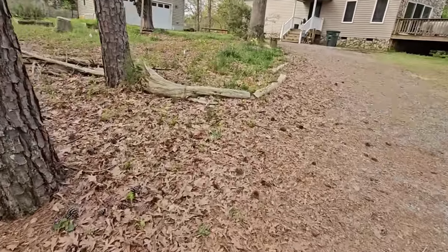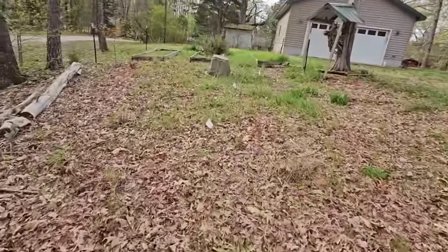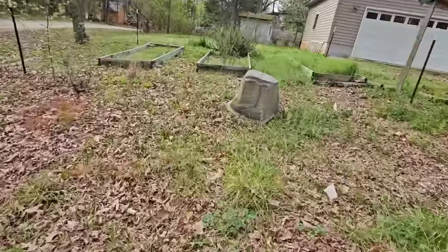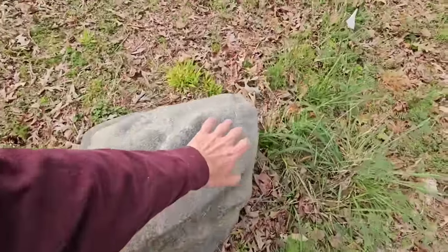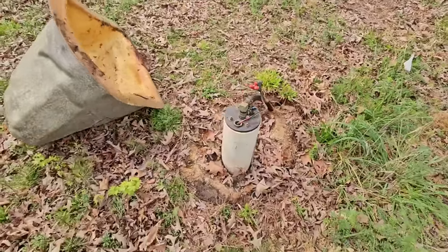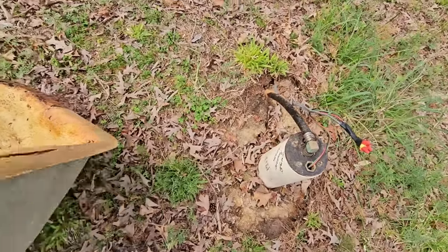We're out here on this job today because the customer said they get muddy, discolored water every time it rains. So typically, discolored water every time it rains is due to surface water leaching into the well during heavy rainfall. It saturates the ground and then it goes down and enters the borehole and brings in the color of the dirt and all that.